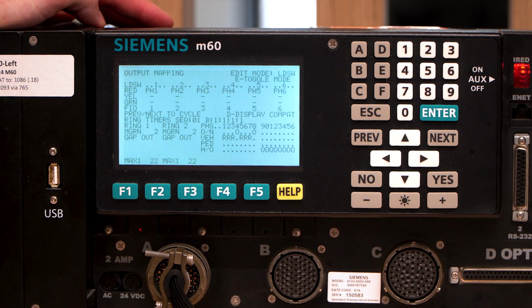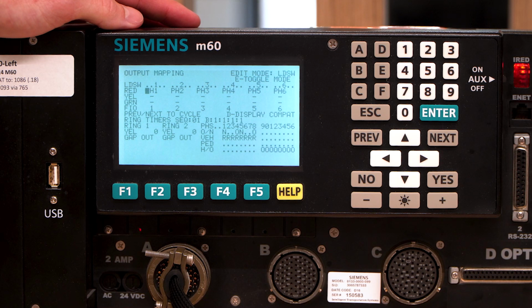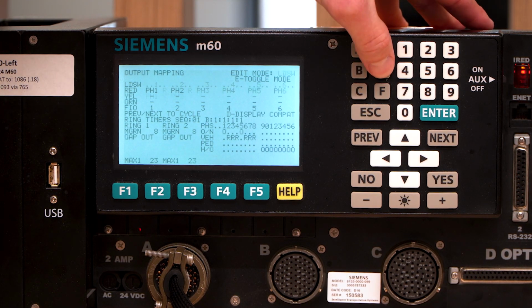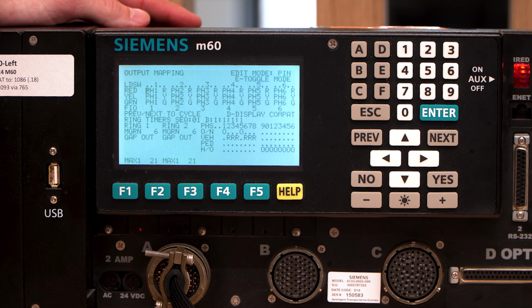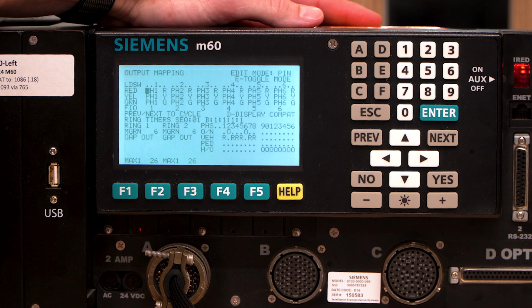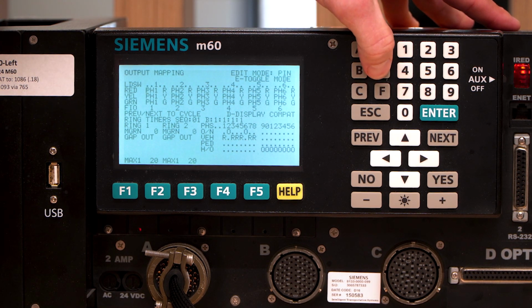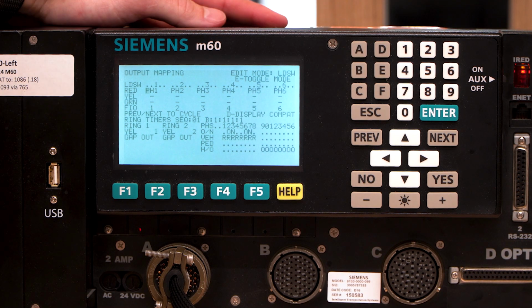If you need to make any changes, you can do so by the whole load switch itself, or you can make pin by pin changes if you need to do so that way. Some customers like to run flashing yellow arrow compact mode, and they would need to go in and make some pin changes to drive the flashing yellow arrow out of the PED channel, or a whole host of other reasons. But you can change the load switch mapping by pin or by the load switch itself by pressing the E key there.